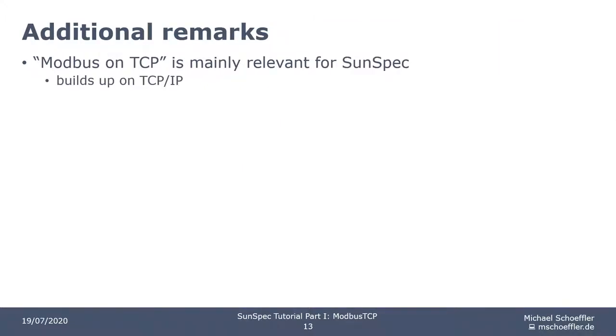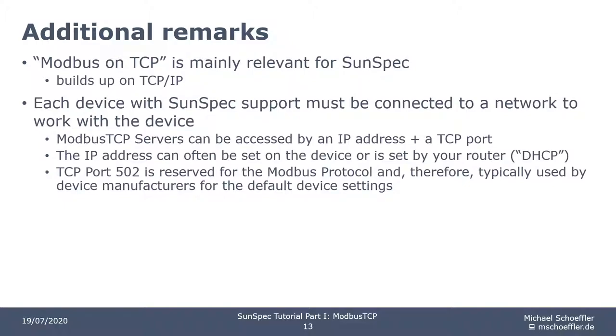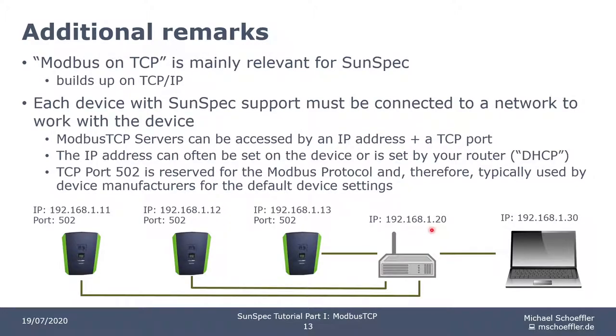Here are some additional remarks that might be important when using Modbus for SunSpec. Mainly Modbus TCP is relevant for SunSpec, and this builds on TCP/IP communication. Each device with SunSpec support must be connected to a network. You can access Modbus TCP servers using their IP address and TCP port. Typically, the IP address can be set on your device, or a router does the job via DHCP. TCP port 502 is normally used for the Modbus protocol and is therefore pre-configured in the default settings of many devices. Here is an example network installation: your notebook accesses three solar inverter devices connected to the same network by a router, all with different IPs but the same Modbus TCP port.